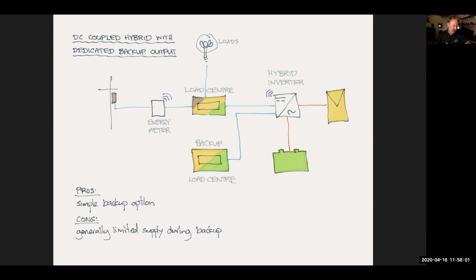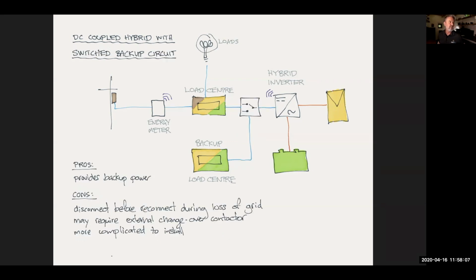All right, so just winding up this presentation. The DC coupled systems with a switched backup, it does provide backup power, but the cons are you will have a loss of power for up to 10 seconds or so, or maybe even longer depending on the ATS. And you may have to provide the external contactor, or it may be built into the device itself. And if it's an external contactor, it will be more difficult.